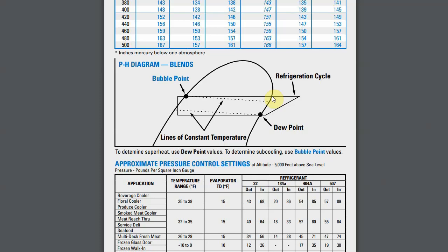And at this point, we are now a saturated vapor. At this point, we start condensing. As we reject heat in our condenser coil, we are condensing, which is why they call it a condenser coil. We're condensing the refrigerant into a liquid. At this point, we have condensed all of the refrigerant into a liquid, so that's its saturation point. Now, here is where we subcool. We're still in the condenser coil. We subcool it to the point where we enter the metering device. This is where we drop pressure. That's what a metering device does. It doesn't change heat content, it just drops pressure.